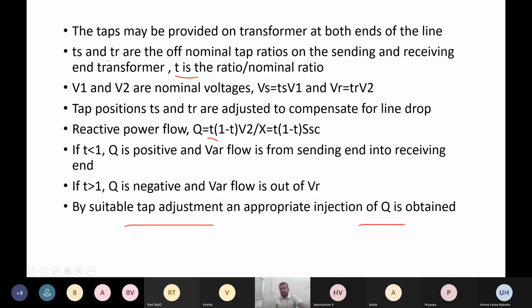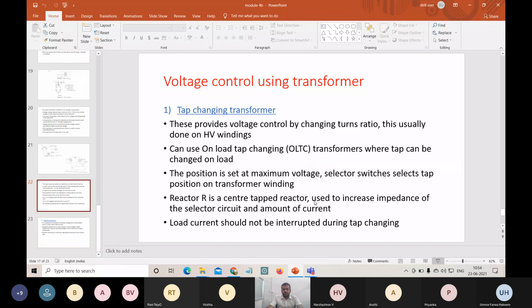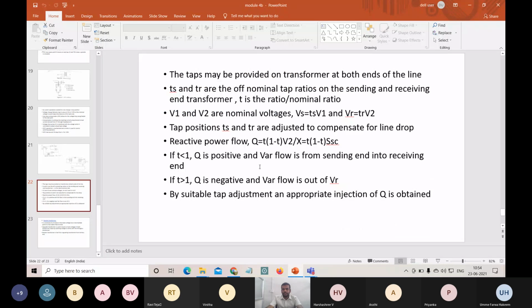So in tap changing transformers, by using suitable positions, by using suitable changes of tap, we can inject the reactive power. We can inject the reactive power by using this form, V square by X. So T of 1 minus T into V square by X. T is our nominal ratio, the tap changing nominal ratio, V square is our voltage, and X is our impedance in the circuit. So we can calculate it by using T of 1 minus T into V square by X.